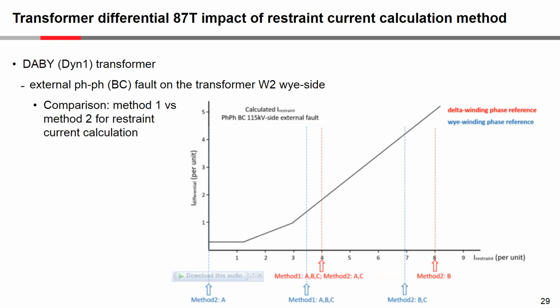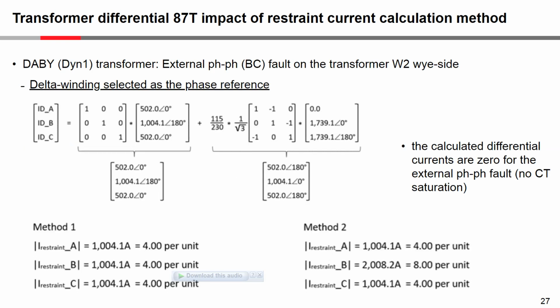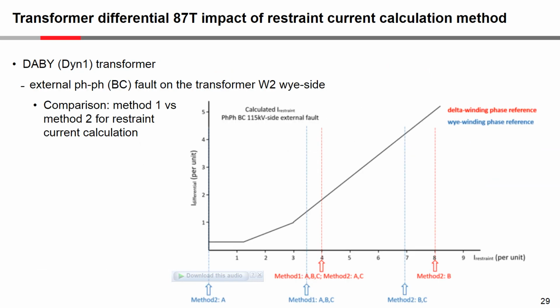First of all, let's look at the delta winding as phase reference. Let me go back quickly here. All right, remember that when we had the delta winding as the phase reference, method 1 and method 2 A and C calculated the same restraint quantity, but method 2 B calculated a quantity that was double. So if we look here, this is method 1, ABC, and method 2 A and C would put you here on the x-axis, and method 2 B would put you at the 8 per unit point.